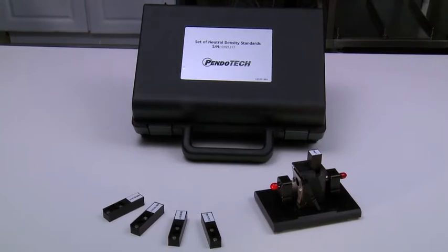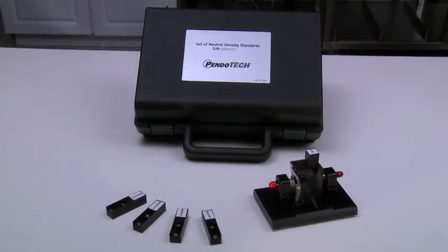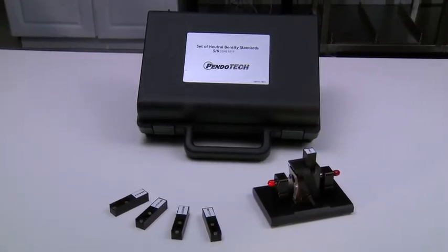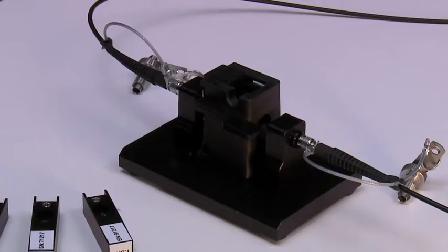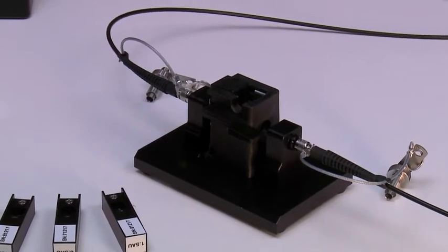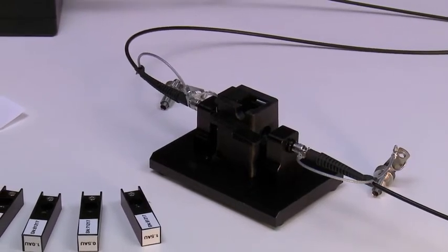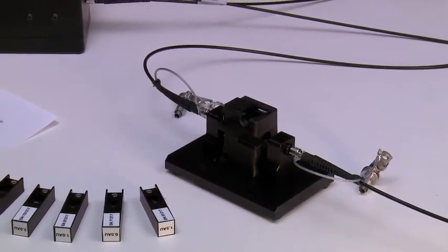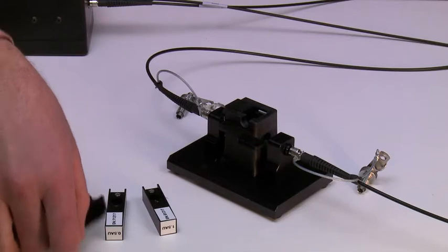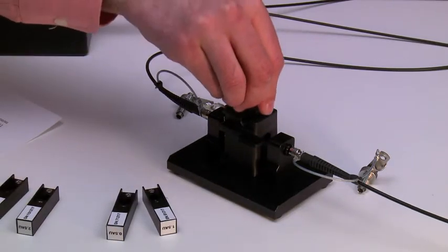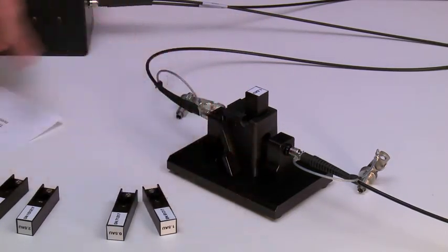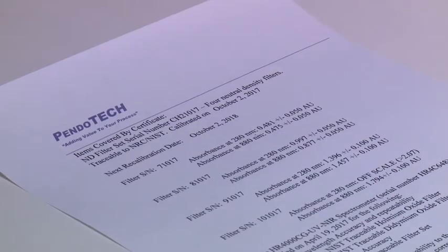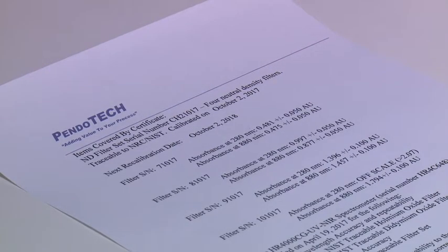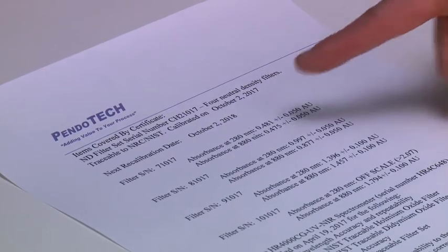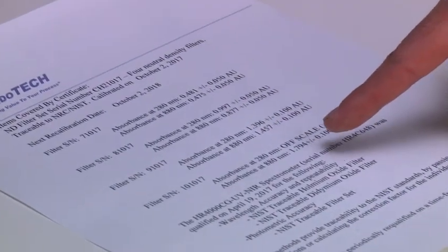Even though no calibration is required, there is an optional test rig to verify proper performance of the photometer. The fiber optic cables from the photometer are connected to the rig, and the light filters from the kit are placed into the holder on the rig, and the absorbance is verified across a range of known AU values of each filter. The filters come with a document that shows their absorbance value for the NIST calibrated spectrometer across a range of wavelengths.